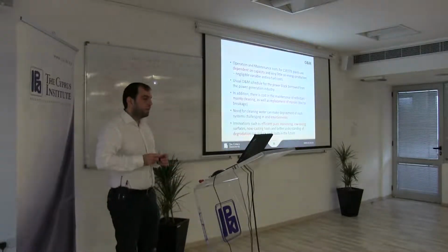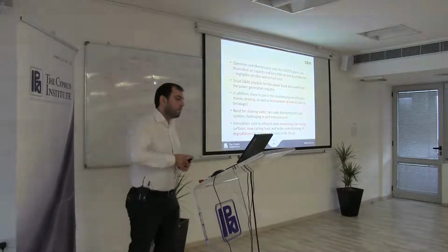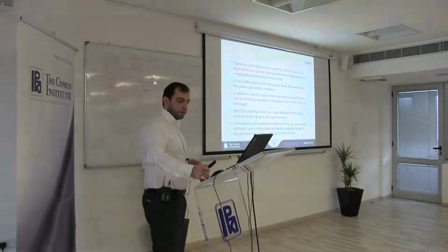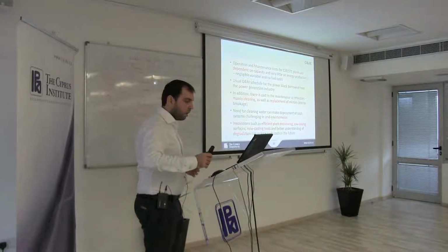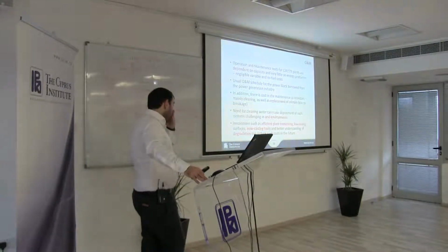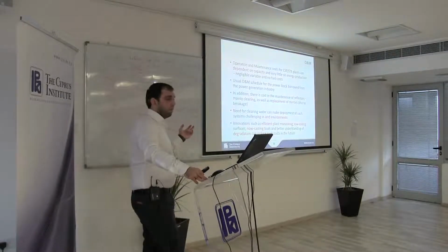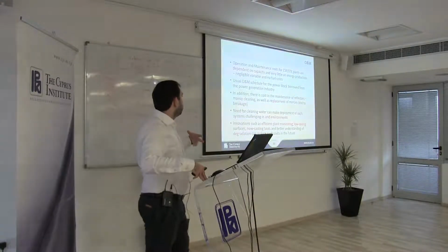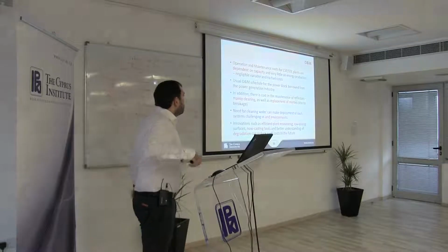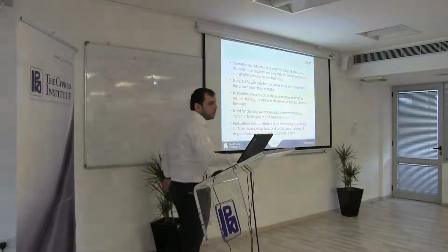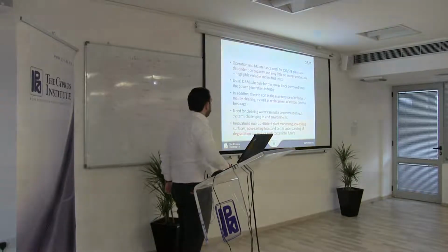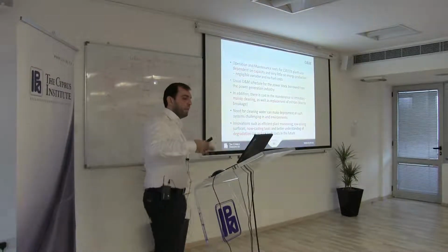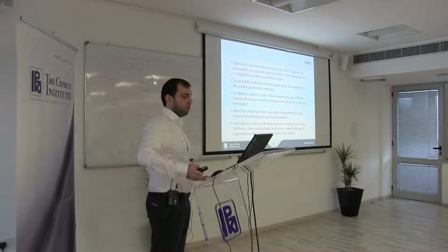In terms of operation and maintenance costs of CSP plants, these are highly dependent on the capacity and not so much on the energy generation. So, as I mentioned earlier, renewable energy technologies don't have very high variable costs. They do have quite high fixed costs, which are related to staff costs, insurance, and maintenance. In the case of CSP technologies, the operation and maintenance is mostly related to cleaning, as well as the replacement of mirrors in case they break.